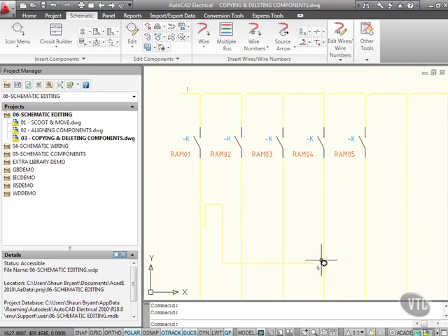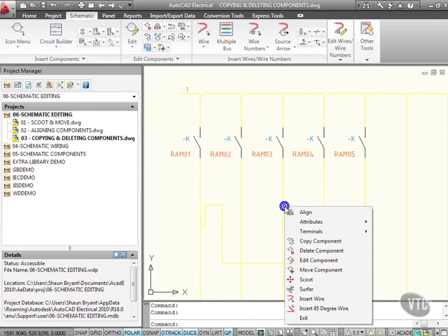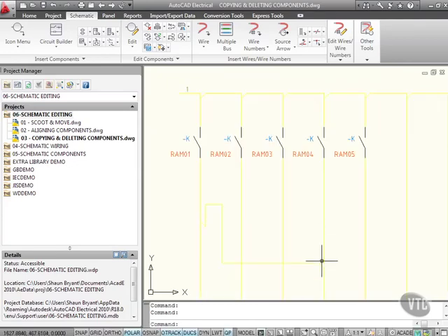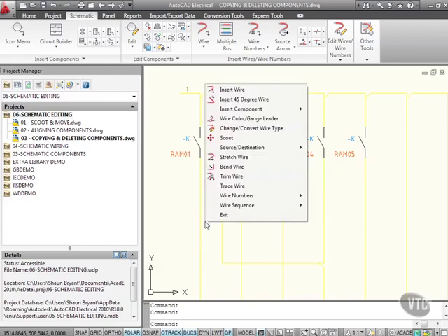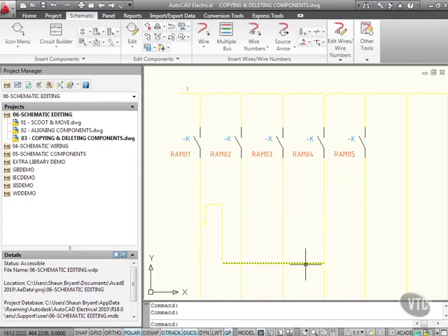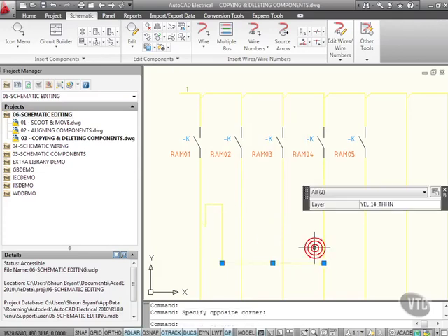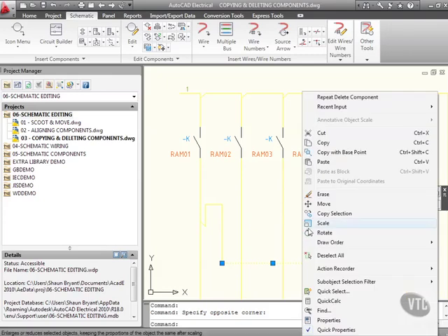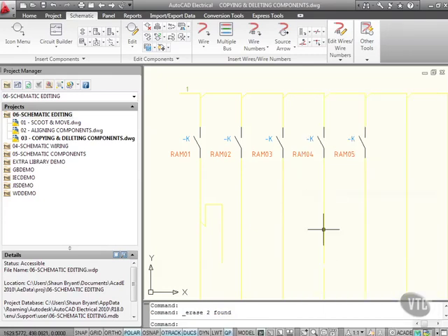So if I now delete terminal 4, what happens? Well, let's watch. Delete component. Just now a connection from one wire there to that wire there. So from that rung there to that rung there. Now, if I select this wire here and right-click, can I delete it? No, I can't. So what I have to do there now is just delete those wires. If I delete those bits there, like that, right-click and erase, does the drawing update? It doesn't. So you need to be aware of that.